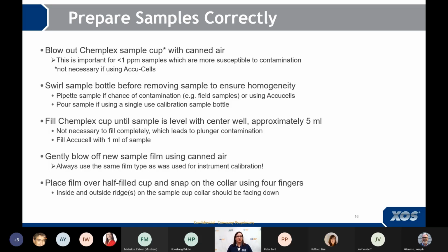Make sure to homogenize your sample bottle. You know this. And actually, you don't need to fill the sample cup all the way up. Five milliliters for the most part is good enough. More sample is not wrong, but may lead to plunger contamination. Make sure you use your canned air to blow off the sample film.